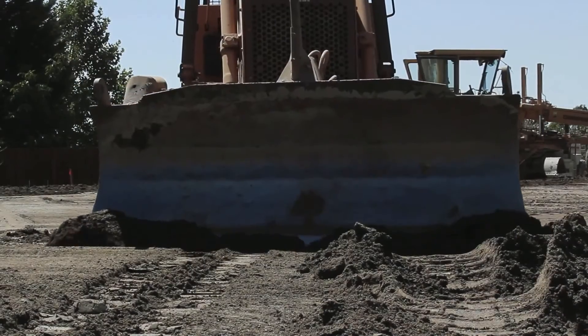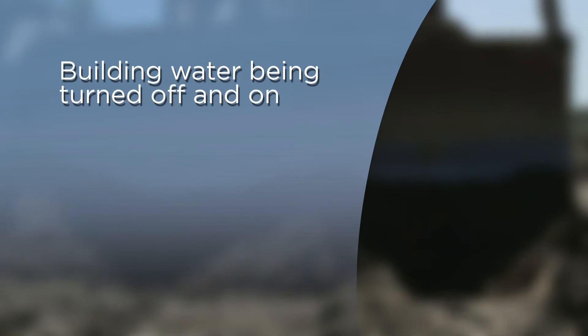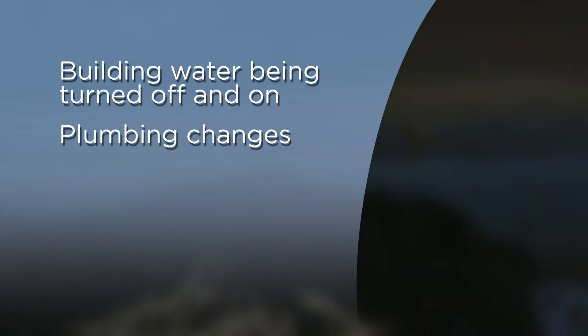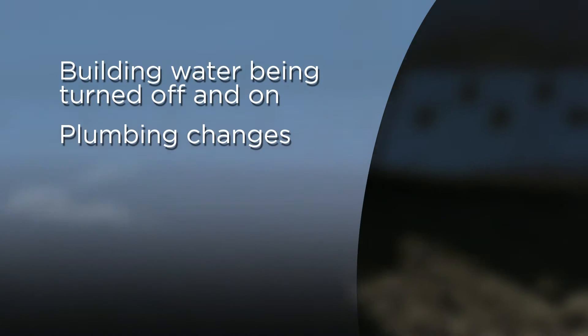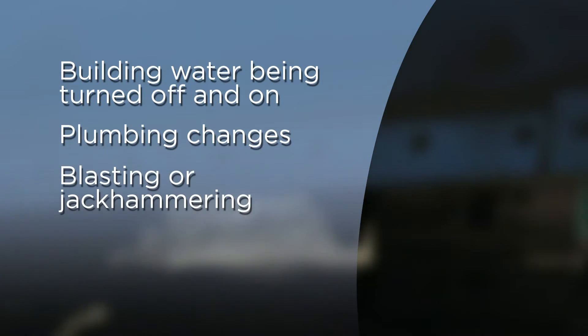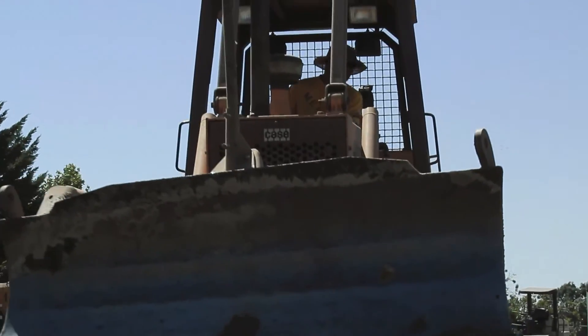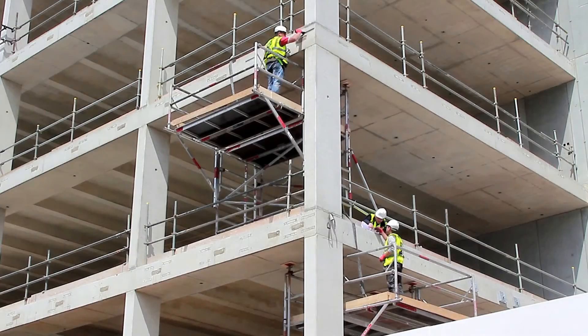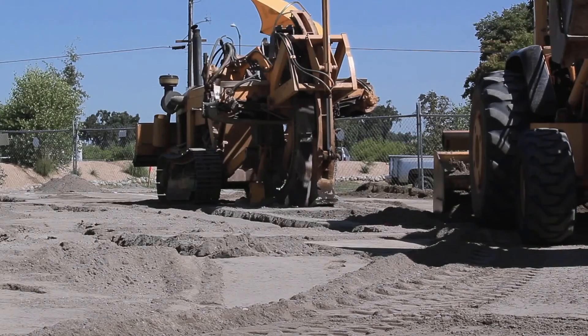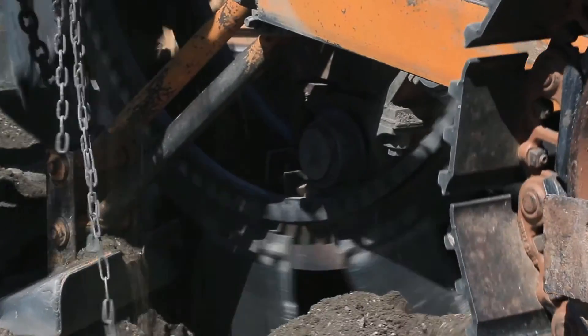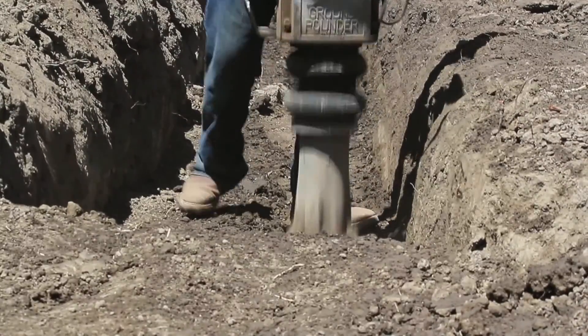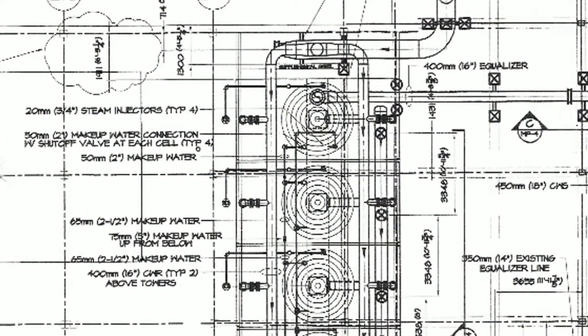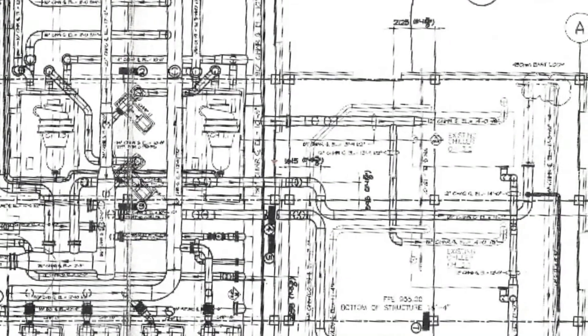The important construction activities to pay attention to include anything that causes the water to the building to be turned off and then turned back on, changes to the plumbing in the building, or anything that shakes the ground like blasting or jackhammering. Note that in densely developed areas these activities may affect adjacent buildings. These can be risk factors because they can cause water interruptions, which can cause changes in water pressure, releasing biofilm, and introduce organic matter into the system. Altering the design of the plumbing system by adding pipes and fixtures can decrease the effectiveness of hot water heaters or disinfection systems.